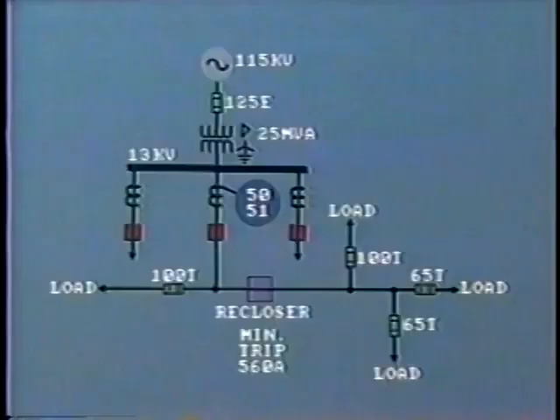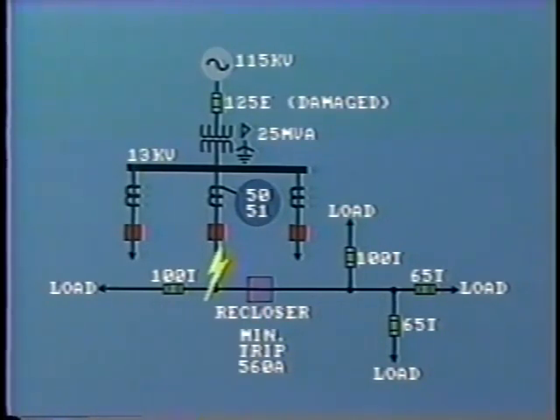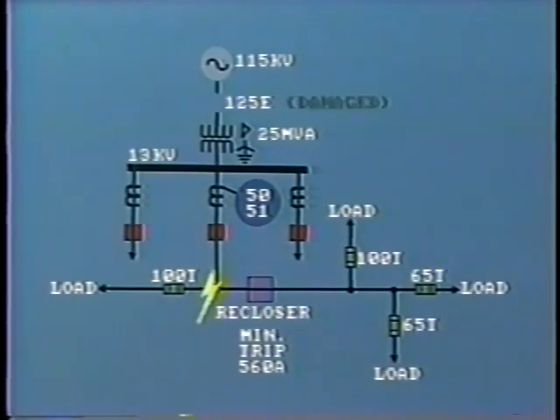Why do we need this? Well, suppose we had a fault, say here, close into the breaker, and the breaker was slow in operating to clear the fault. The high voltage fuse elements would start to melt and become damaged. Before the fuse element melts open, the breaker may eventually open and clear the fault.